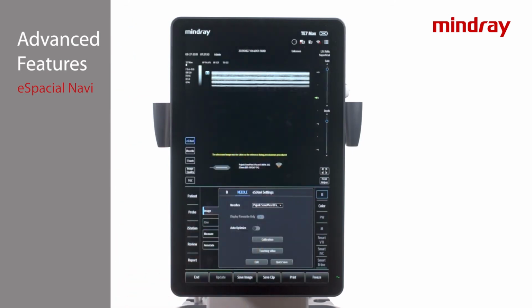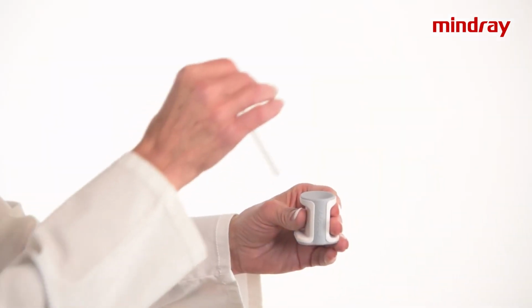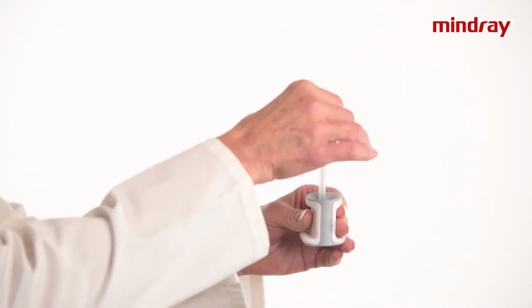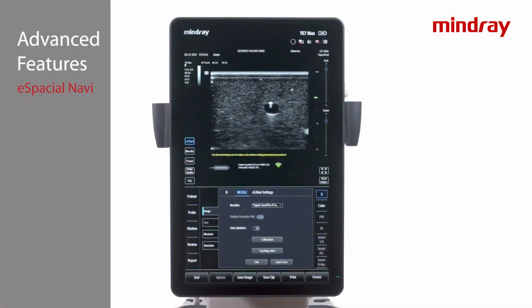Recalibration should only need to be performed once each day or if a different needle is chosen from the list. Magnetize the needle by placing it in the magnetizer with the cap on, all the way to the bottom for a second, and pull back out. Notice the trajectory or dotted line on the screen before touching the patient with the needle. For out-of-plane procedures, change angle and degree of the needle to alter the target box location. Advance the needle toward the target. The top yellow dot is the needle tip.